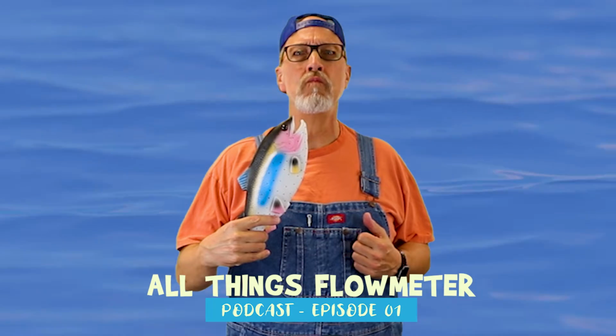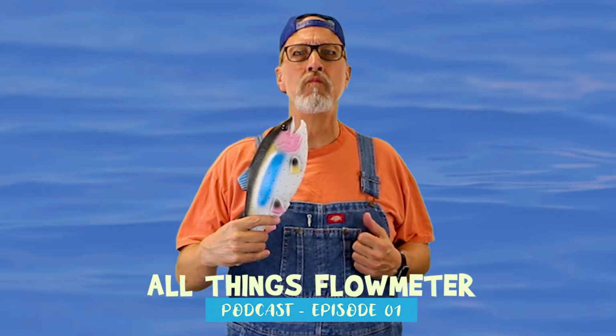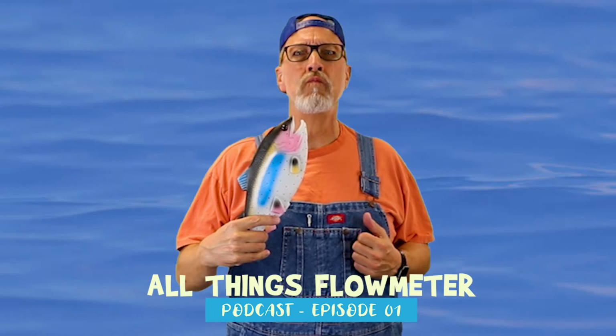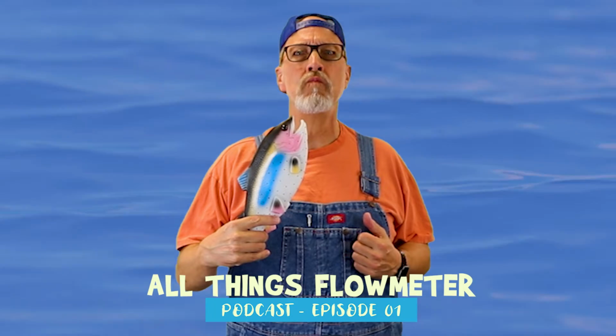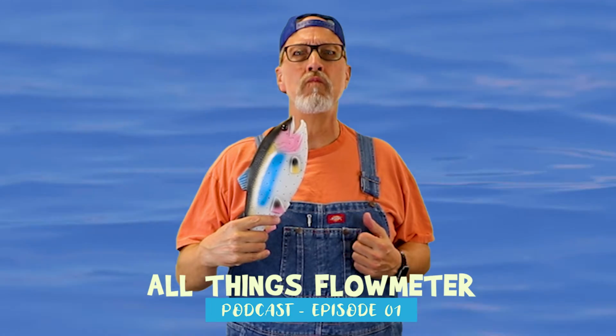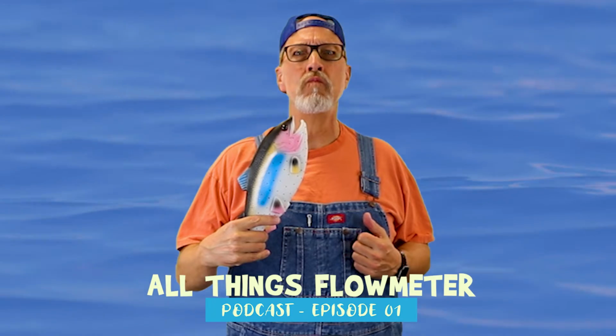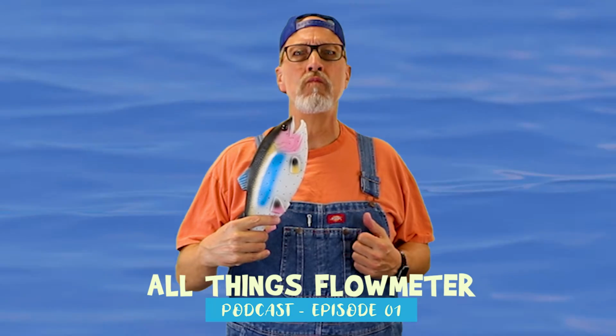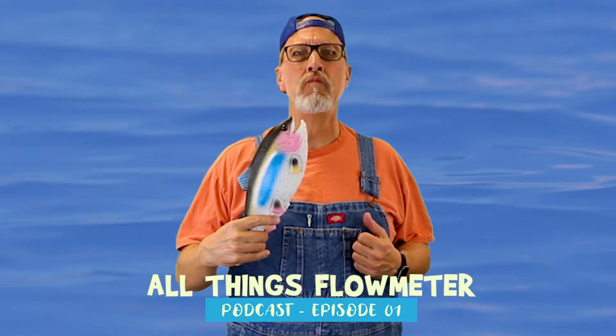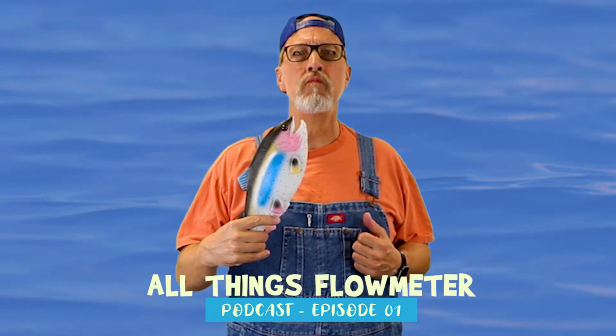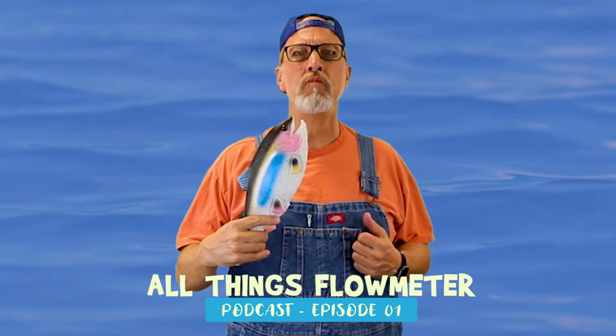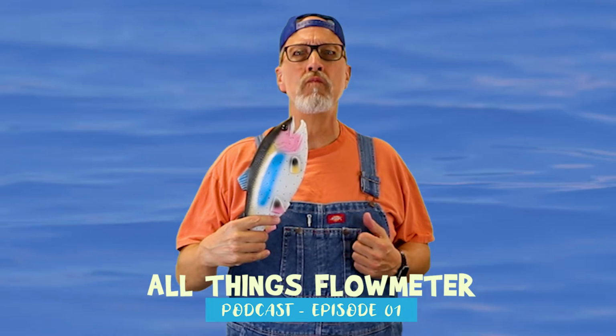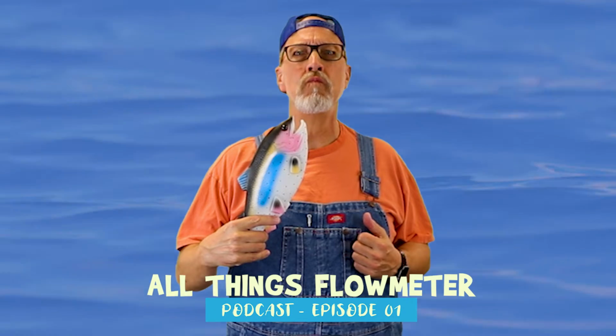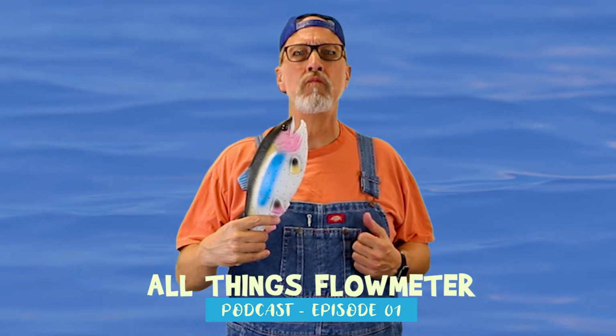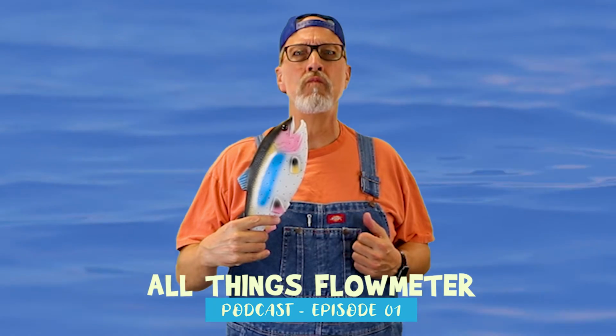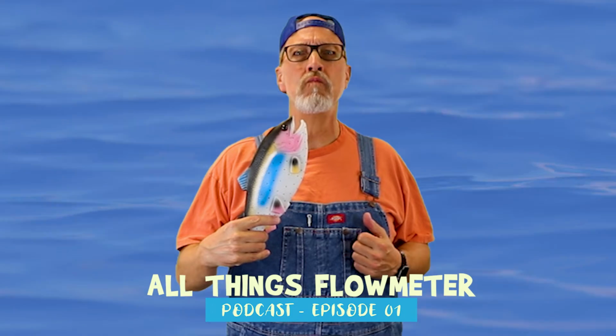And you mentioned earlier, a lot of times these meters will feed into some sort of feed equipment so we can dose our products. Not all meters have that capability. So what do we need to look for if we're looking for some sort of pulsing meter? Well, most flow meters will have, well, not all flow meters. It's an option. So if you just got a traditional water meter, it's not going to have a pulse output. It'll be a reed switch kind of output. Then you'd have to get one that actually has that feature, a pulse output. The next step output you would get from that would be a 4 to 20 milliamp signal, an analog signal, and they would also have a pulse output. So most of the ultrasonic and the magnetic come with all that standardly. The lesser the price of the meter, it's usually an option whether it has a pulse output or not. And that'll go to some type of a controller.